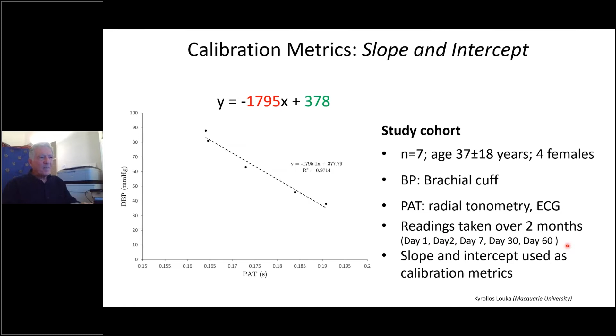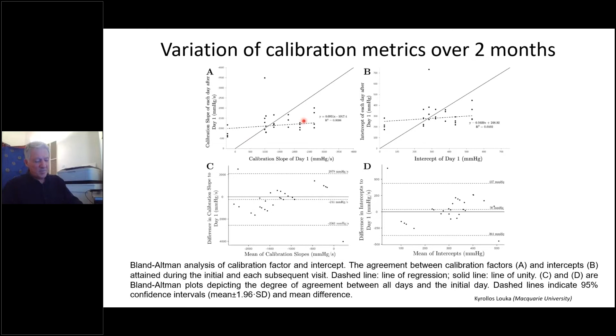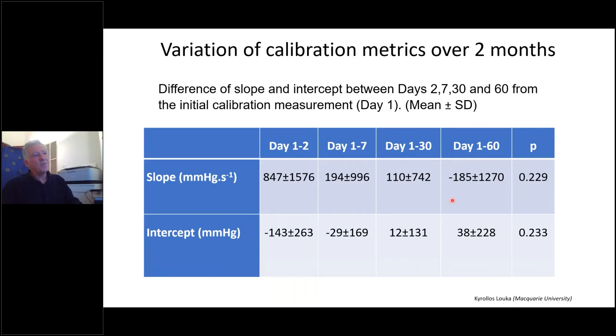So again, this is a potentially complicated slide, but it's not. This is calibration, the slope of compared to day 1, right? If they were the same, all the points would lie on this curve here. So these slopes change with different days because compared to the day 1, they're different. That's what this means. And so this is the variation of these slopes and intercept, that day 1, day 2, day 30, and day 60 compared to day 1, very different. If one were to do a statistical test on these, you would say no difference. So the statistics say those calibrations are all okay, but in fact they're not. If we use those calibrations in individuals, we will get hugely different values of derived cuff pressure for those calibrations on those different days.